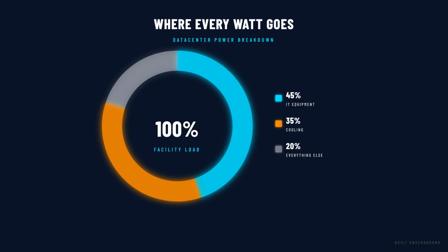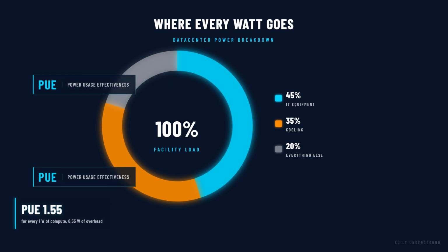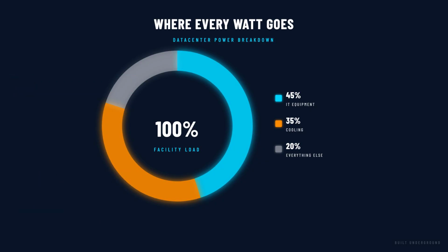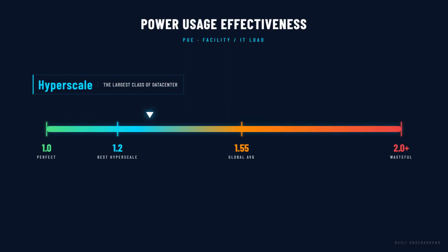A PUE of 1.0 would mean perfect efficiency, every watt goes to computing. The global average is around 1.55, meaning for every watt of computing, the facility uses an additional 0.55 watts just to keep everything running. The best hyperscale facilities achieve PUEs of 1.1 to 1.2. Some older enterprise data centers still run above 2.0, meaning they waste more electricity on cooling and overhead than they use for actual computing.